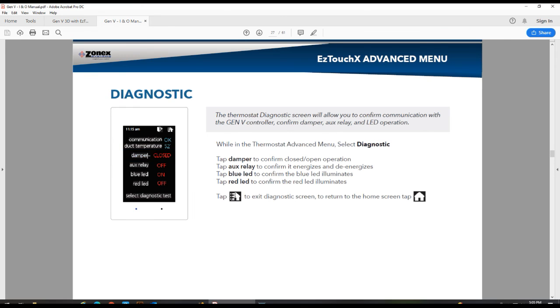So to change it, you just tap on damper, and it will say closed. Tap on it again, it will say opened. If you want to confirm that your auxiliary relays are working and that your auxiliary heat is energizing, you can go ahead and turn it on, and it will go ahead and energize that 24 volt output. Each thermostat has a red LED and a blue LED. These illuminate when there are calls from the thermostat, so you can turn them on and off and confirm those LEDs do illuminate at the bottom of your thermostat.